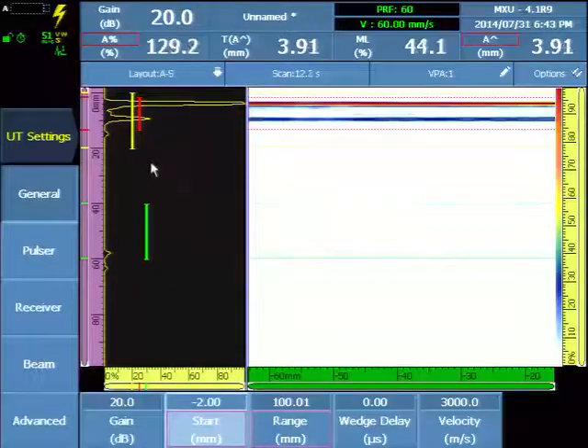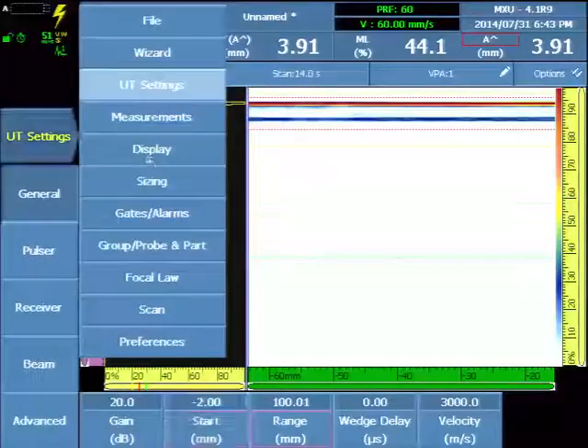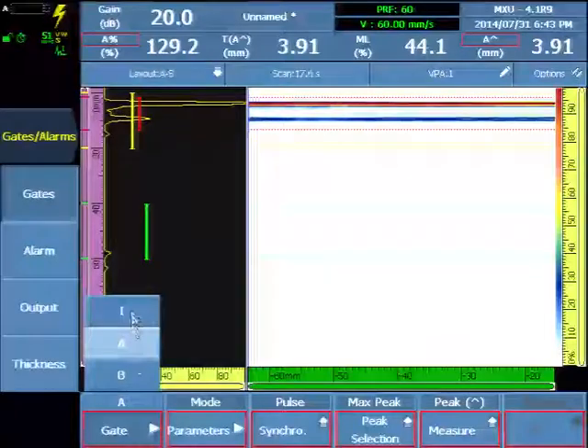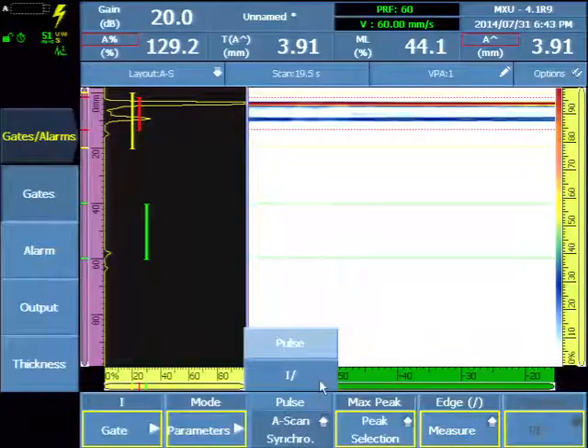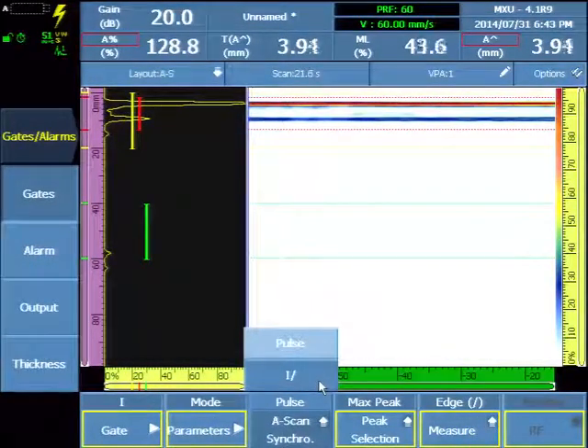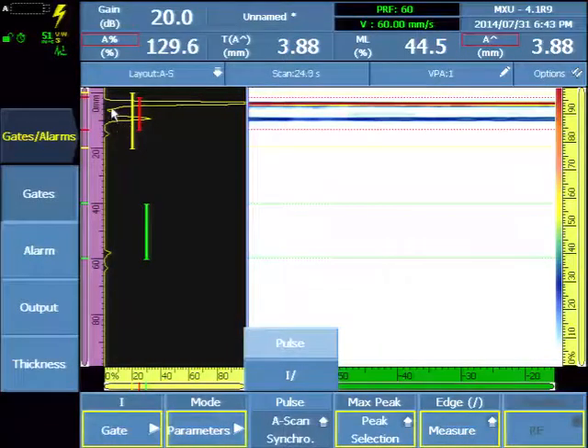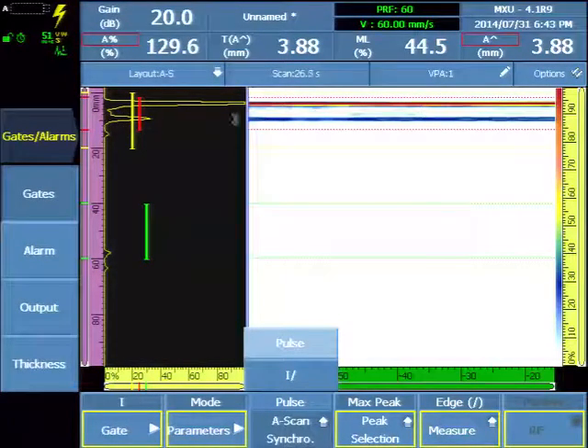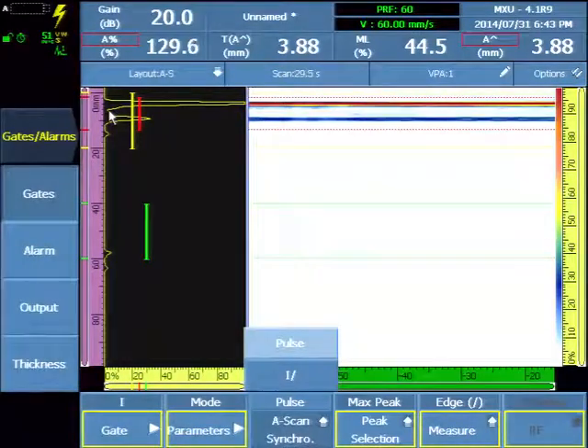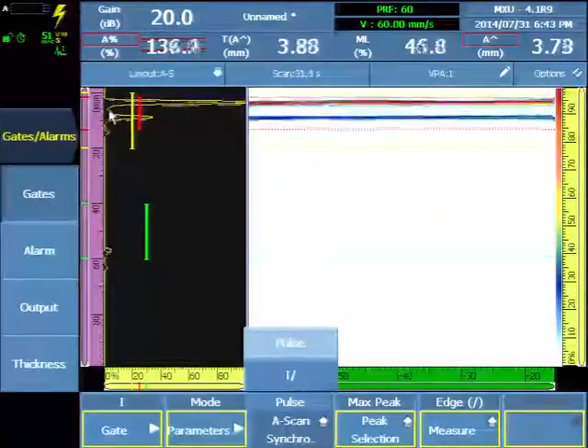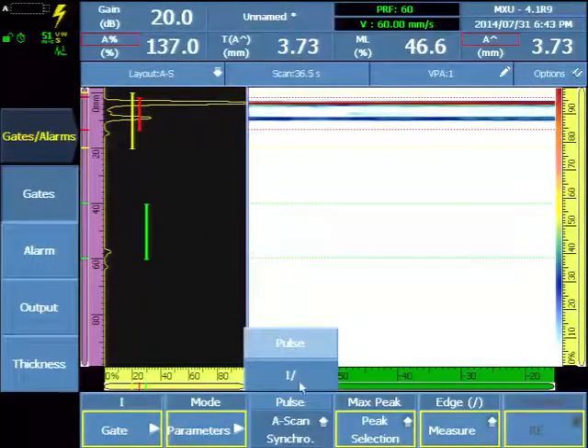The synchronization gate, the yellow gate, is used similar to an immersion tank and it has a function called synchronization on echo. It will dynamically adjust the position of all A-scans or focal laws to 0 mm so that as the probe is moved and pressure changed the interface will stay straight and flat. So we'll switch to synchronization on echo.